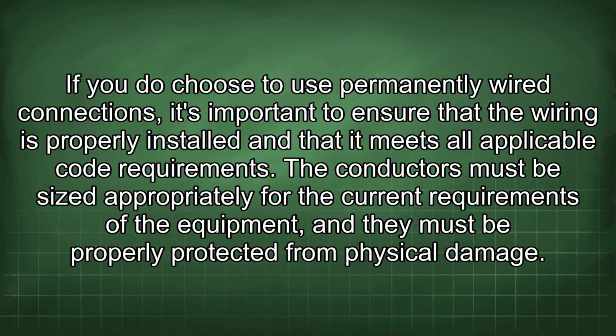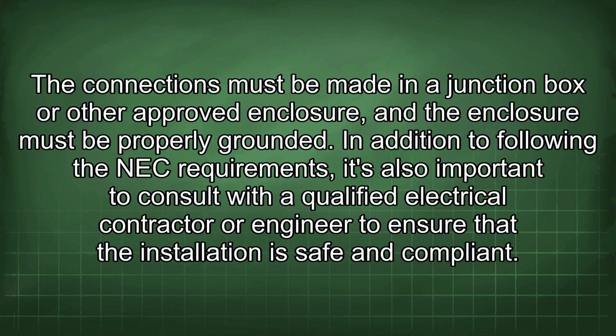If you do choose to use permanently wired connections, it's important to ensure that the wiring is properly installed and that it meets all applicable code requirements. The conductors must be sized appropriately for the current requirements of the equipment, and they must be properly protected from physical damage. The connections must be made in a junction box or other approved enclosure, and the enclosure must be properly grounded. In addition to following the NEC requirements, it's also important to consult with a qualified electrical contractor or engineer to ensure that the installation is safe and compliant.